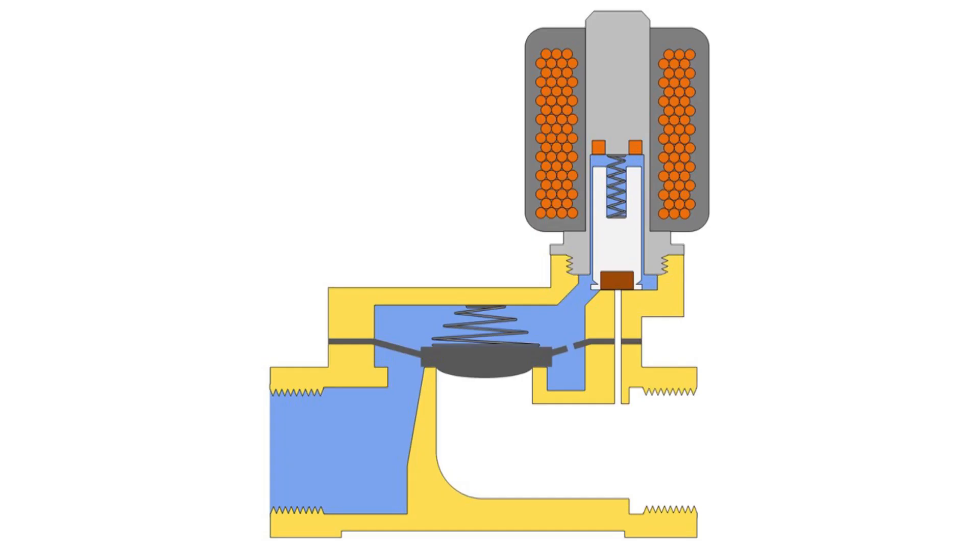Symptoms of coil defects are usually burn marks, cracks, cold when powered, infinite resistance, or if you don't hear a click in the valve when energizing.